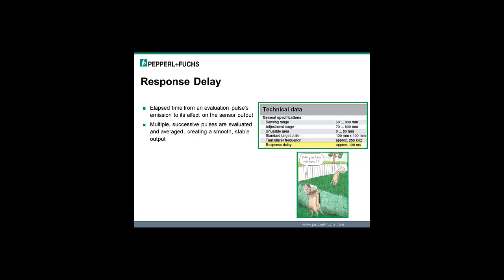It sends out its pulse, and then internal to the sensor, what it's really doing is it's probably going to take like 4 or 5 different pulses, successive, 1, 2, 3, 4, 5, and it's going to average them. So that way your output doesn't jump up and down as it gets each echo back. It averages those 5 out and then gives you the output, and that makes for a very smooth, stable output. So that's another reason why an inductive sensor or a photo eye might have a 1 or a 2 millisecond response time, and the ultrasonic is going to have 100. It's because it's taking multiple pulses, averaging them out, and then it's triggering the output to do whether it's analog, switch point, whatever the type of sensor is.